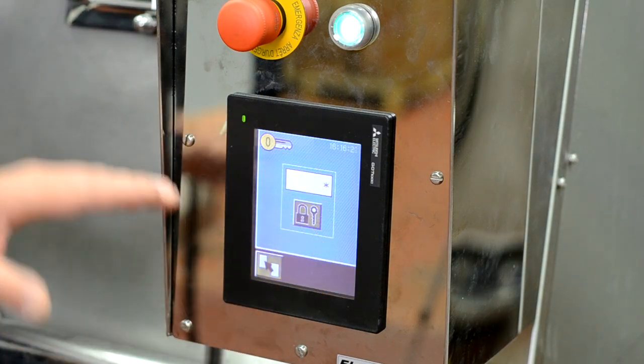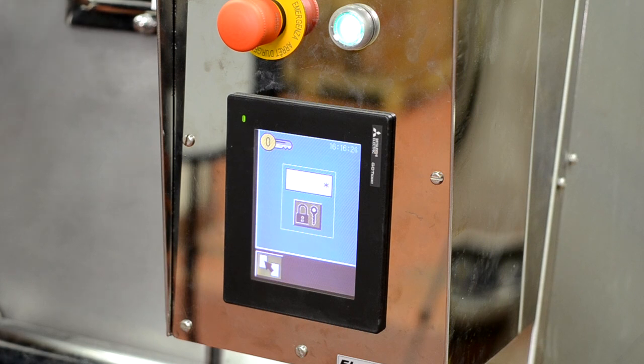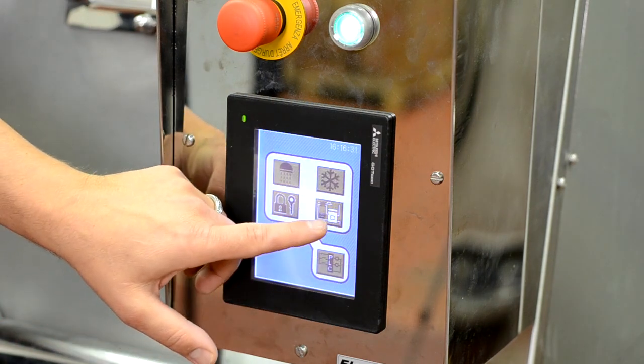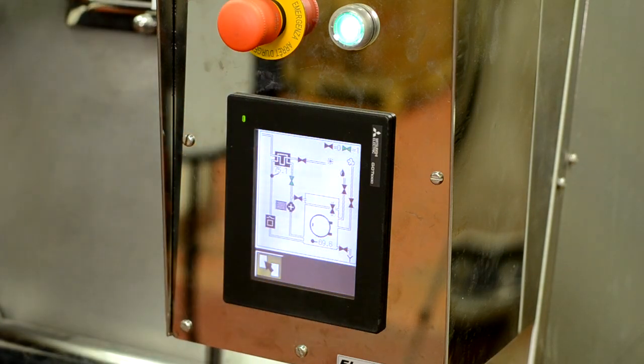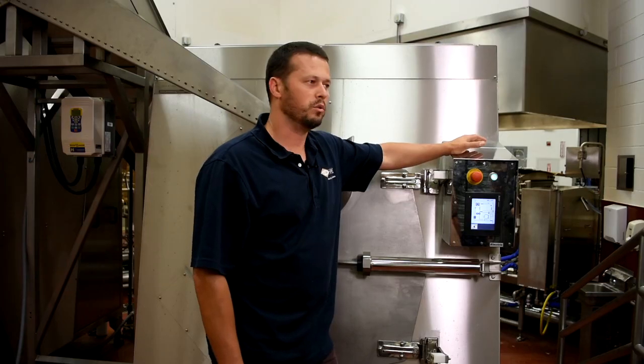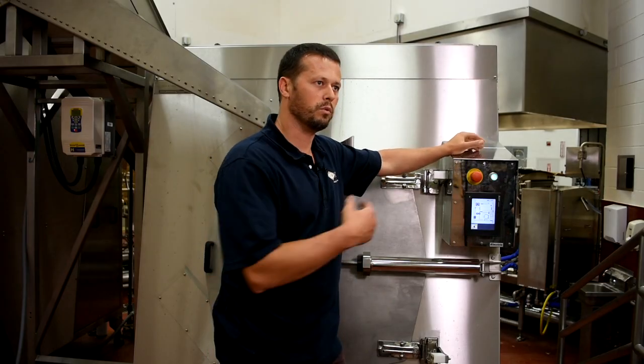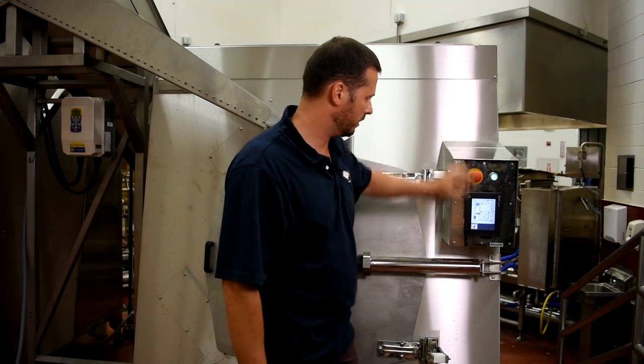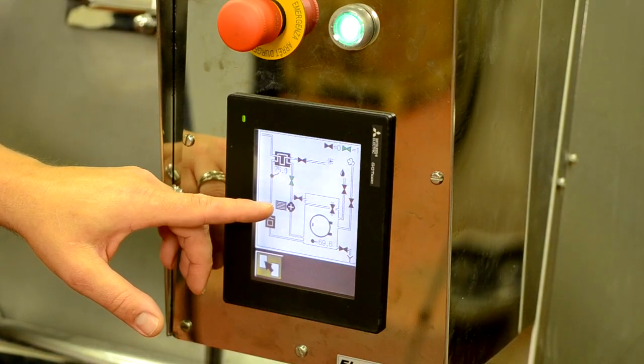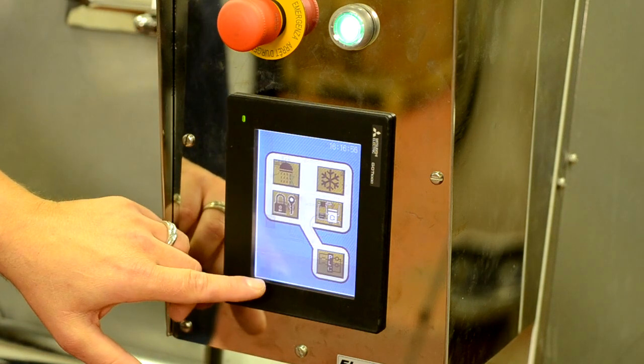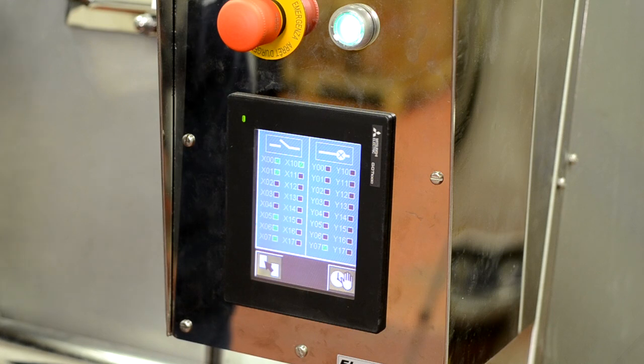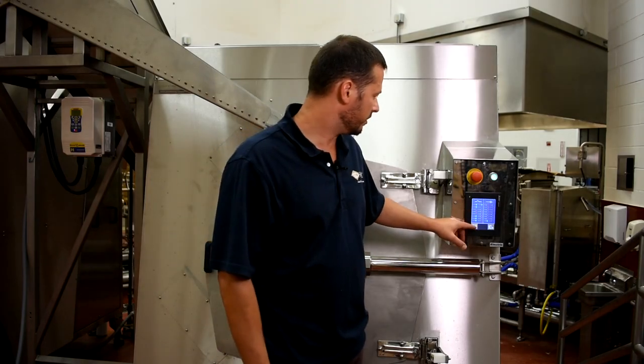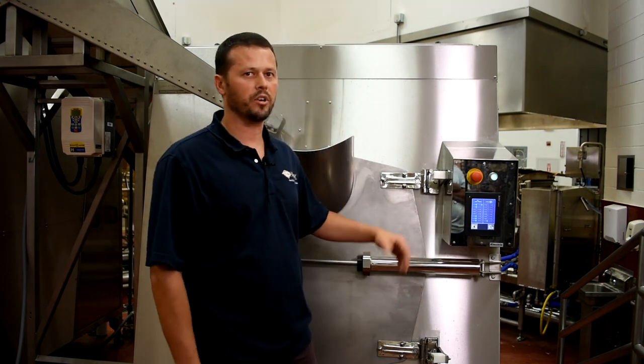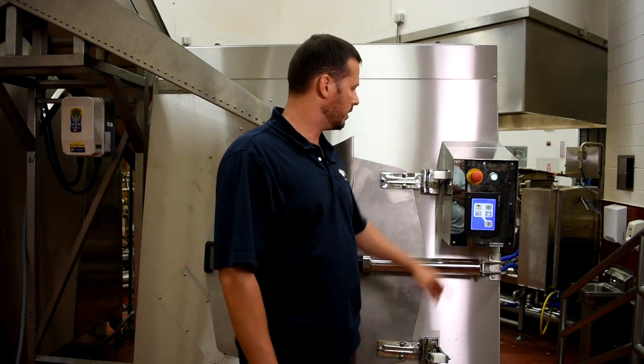Right here is our passwords. From a manual, we can set different parameters or different level access for operators. For troubleshooting purposes or for maintenance, you can see clearly which valve is on, which valve is off. So this screen comes in very handy to see how the machine is operating, which state it was at, and if we're having any issues, we can look at this little schematic. This is live time, so this will show you what's happening while the machine is running. And then here again, this is more for maintenance. You can see which valves are on, which inputs and outputs in the PLC are on or off. But for the operators, this is your main screen.